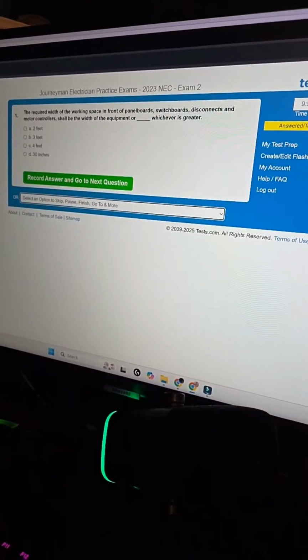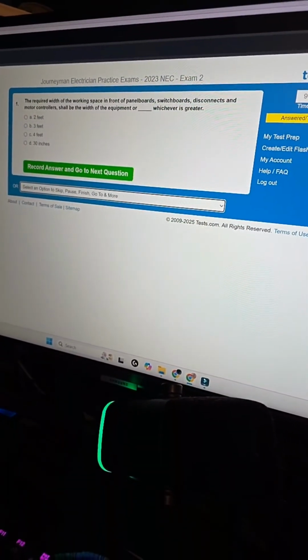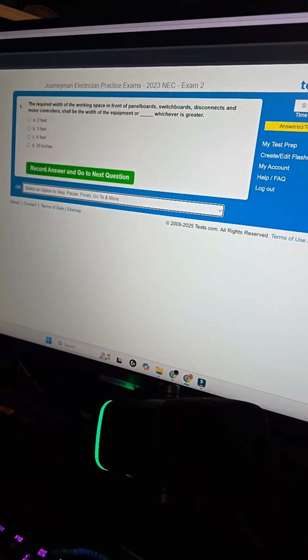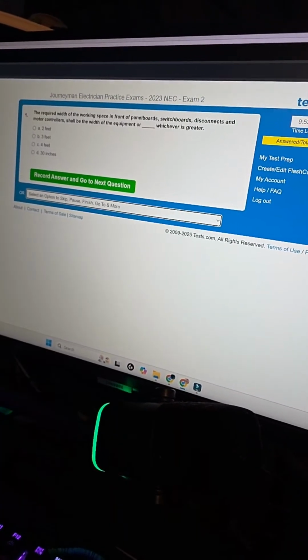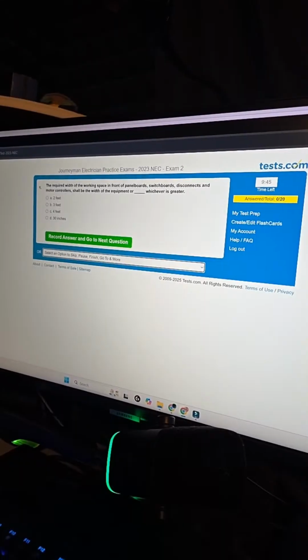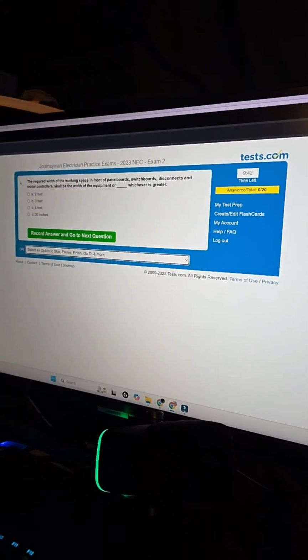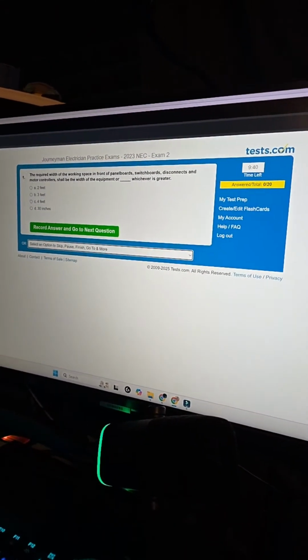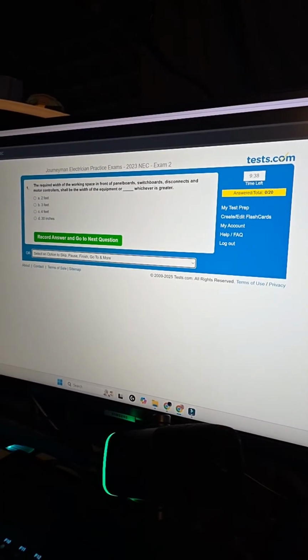Got a camera holder here for the phone, and I can read that through the phone. It says the required width of the working space in front of panel boards or switchboards, disconnects, and motor control center shall be. So we know that it's 30 inches side to side, and we know that it's 36 front to back. And we are experimenting with this, so we're going to see if this thing's going to stay or is it going to try and fall the whole time.